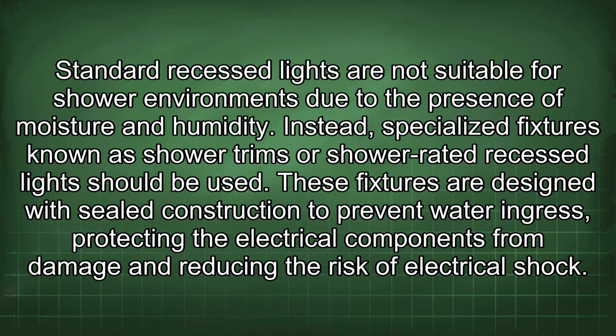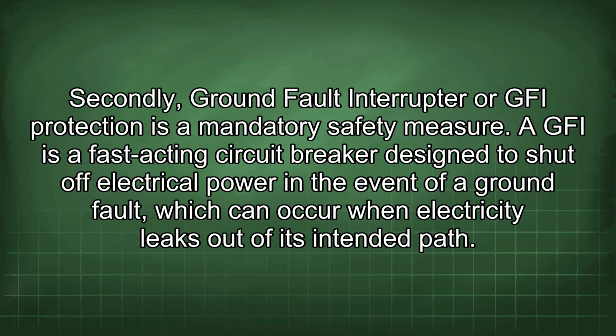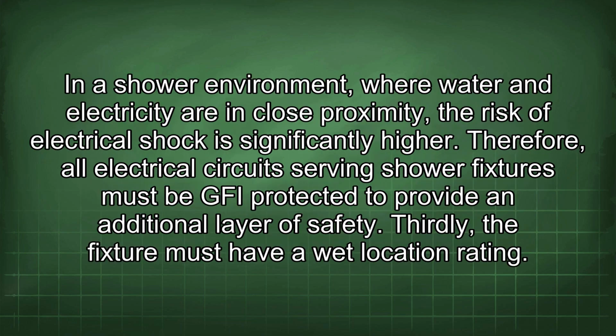risk of electrical shock. Secondly, ground fault interrupter or GFI protection is a mandatory safety measure. A GFI is a fast-acting circuit breaker designed to shut off electrical power in the event of a ground fault, which can occur when electricity leaks out of its intended path. In a shower environment, where water and electricity are in close proximity, the risk of electrical shock is significantly higher. Therefore, all electrical circuits serving shower fixtures must be GFI protected to provide an additional layer of safety.